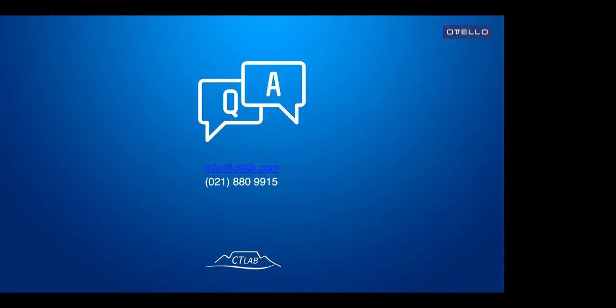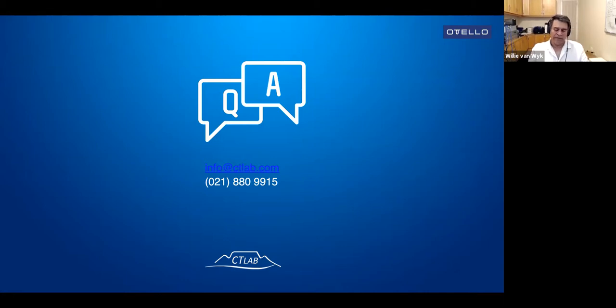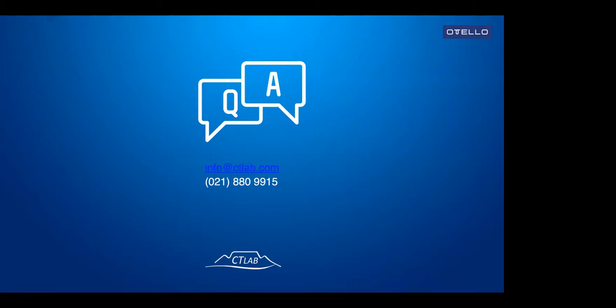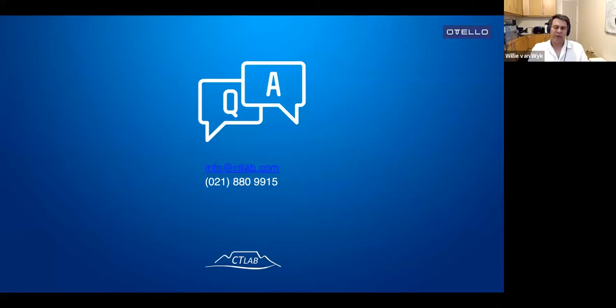Thanks, Willie. I just want to say another one. On each one of the devices, we have a virtual development environment. It's called Lua. It's something similar to Visual Basic. But one of the PhD students at Potch University implemented a complete slipping pole protection relay within that space. So that virtual machine on board of the device itself, keep in mind it's an edge computing device, means we can add a lot of intelligence there. And that environment has access to raw waveforms, Ethernet, the filing system, the relays, the digital inputs, all of that is accessible.